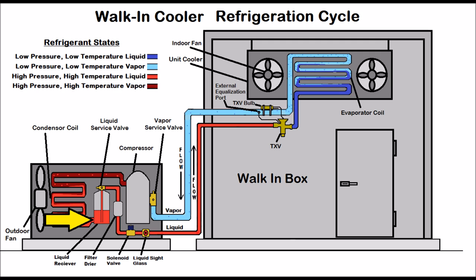When you start a walk-in box up for the first time, that liquid receiver should be drained just about all the way down to the bottom. You should have a solid column of liquid heading through that liquid sight glass — that verifies you still have enough sub-cooled liquid heading to the TXV. But you don't want to add extra refrigerant that will be stored in the liquid receiver.